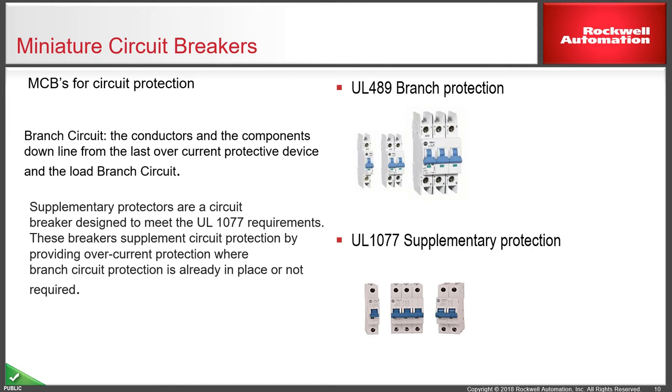Miniature circuit breakers inside the panel can be the UL489 version for branch protectors. You'll notice the breaker is slightly taller in design than a standard circuit breaker for the European market, as it has extended fins at the top for cable guidance, separation, and segregation. These can be used as the overcurrent protection device on the load branch. The supplementary 1077, as the name implies, must be used in addition to another breaker — typically on the output of a power supply or ancillary equipment downstream of a main branch protector.